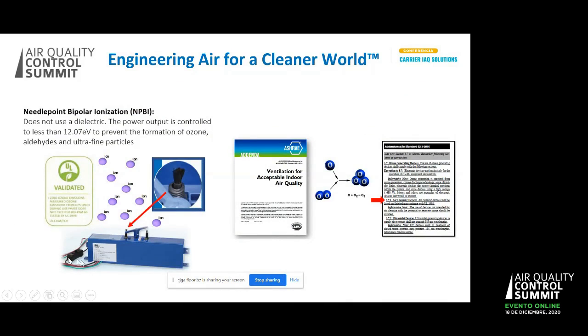What we do with needlepoint bipolar ionization is simply impart that electrical ionization of the air directly to the air off of needle points that are exposed to the air off of the device itself. These needle points are made out of carbon fiber material, the same material that we make airline fuselages out of, for example. So it is very durable, very robust, very corrosion resistant. It does not wear out or wear down over time, and it's a very great source to energize the air from based on its electrical conductivity. And because of the way that we impart the ions to the air through these needle points, we create an abundance of ionization without creating byproducts of concern such as ozone.